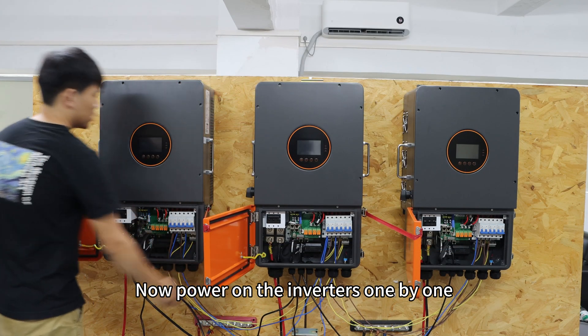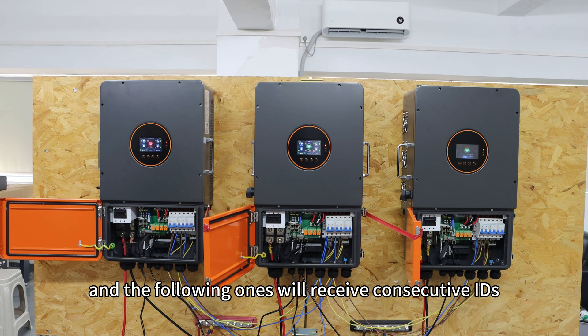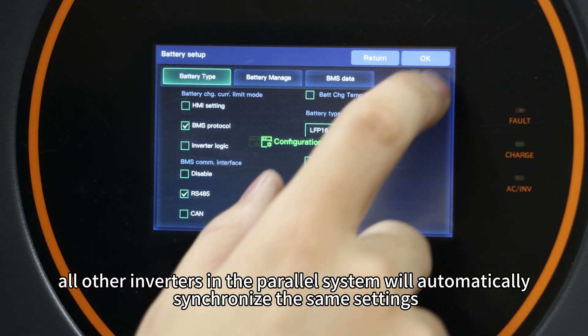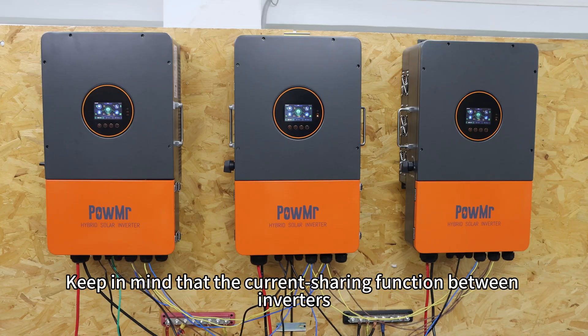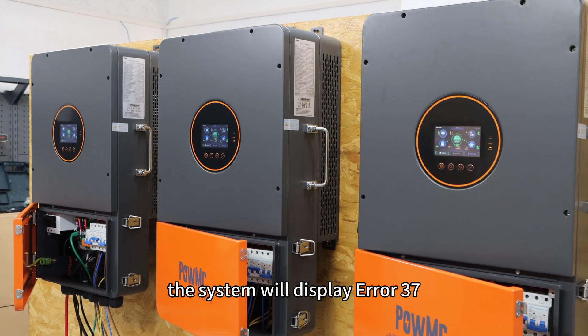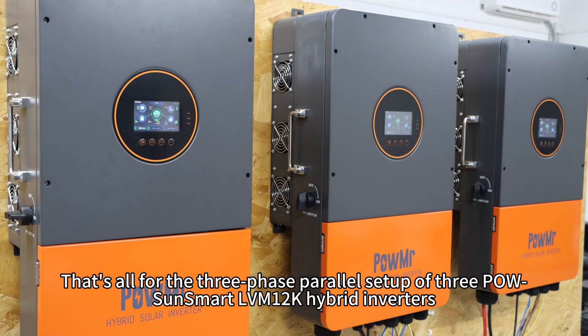Now power on the inverters one by one. Once connected to the battery BMS via the communication cable and the battery type is set on any one inverter, all other inverters in the parallel system will automatically synchronize the same settings. Keep in mind that the current sharing function between the inverters only works after their AC output ports are connected. Before the load breakers are closed, the system will display error 37, which will clear automatically once you close the load breakers.